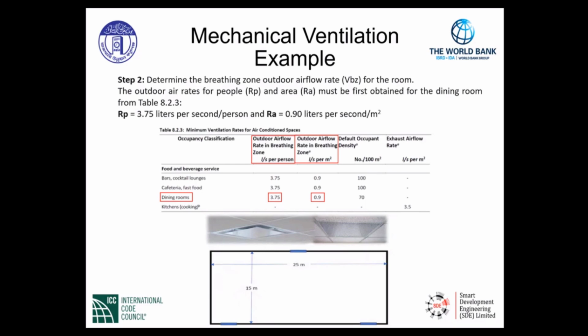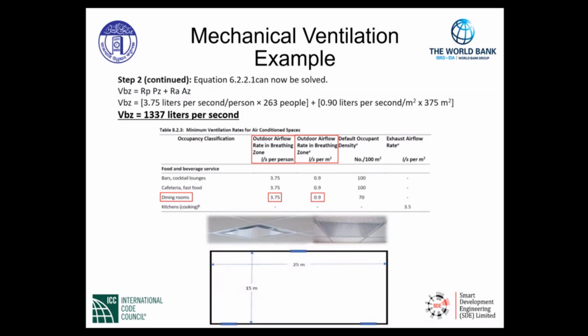As indicated in the table below, the R sub P value, the outdoor airflow rate in the breathing zone in liters per second per person, is given to us at a rate of 3.75 liters per second per person. And in the adjacent column, the outdoor airflow rate in the breathing zone for the area is given to us as 0.90 liters per second per square meter. So we select those two values for our dining room in step 2. A continuation of step 2 now gives us our equation. Equation 6.2.2.1 can now be solved.